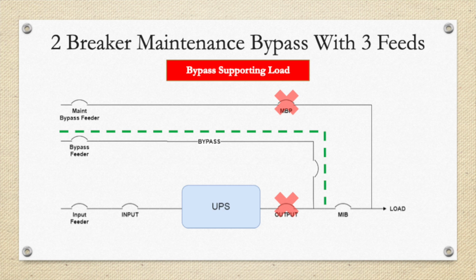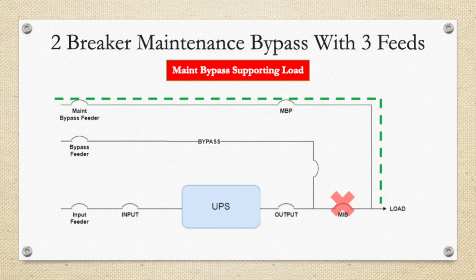Next drawing shows that configuration running in internal bypass. So we're running through the internal bypass and out of MIB with MBP off. Now we can operate the maintenance bypass. So by doing so, we're going to close MBP, open MIB, and now the next drawing shows us running on the maintenance bypass mode on this system. Again, we can totally de-energize the UPS. We still have the ability to load test this UPS while still maintaining the critical load on the maintenance bypass circuit.